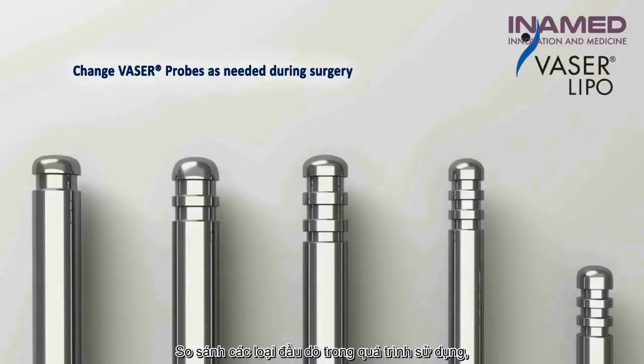For comparison purposes, a 3-ring 3.7 mm probe distributes approximately 70% of its energy from the sides and 30% from the front surface. A 2-ring 3.7 mm probe distributes approximately 50% of its energy from the sides and 50% from the front surface. A 1-ring 3.7 mm probe distributes approximately 30% of its energy from the sides and 70% from the front surface.